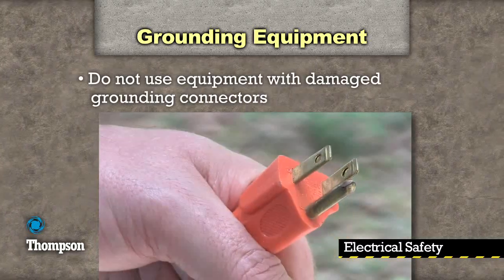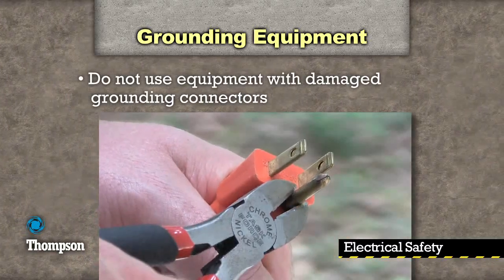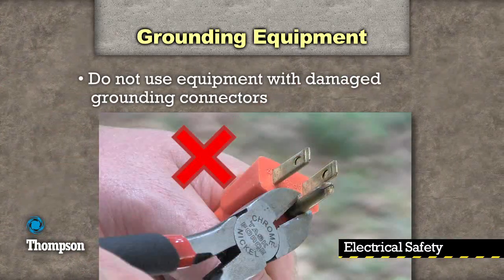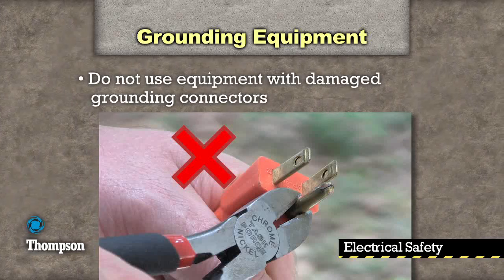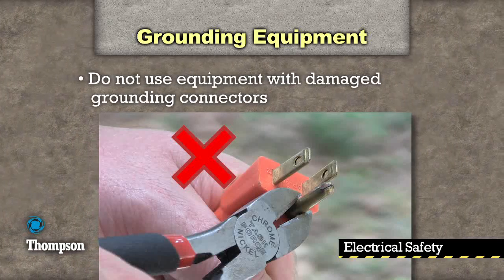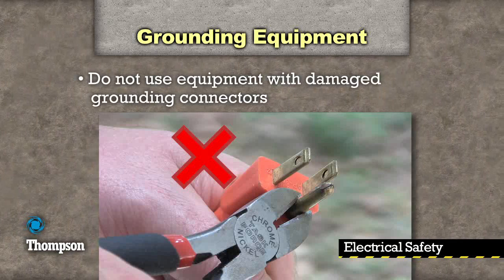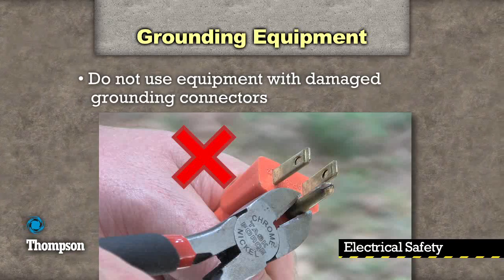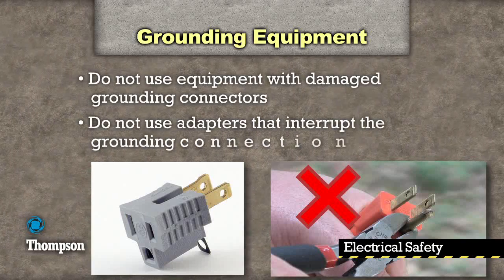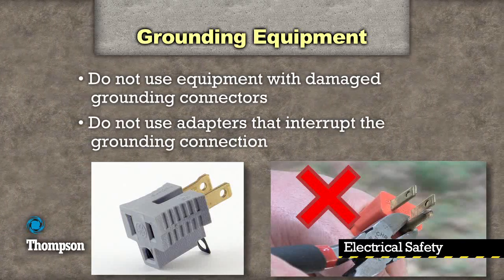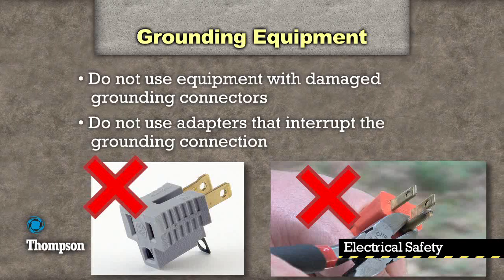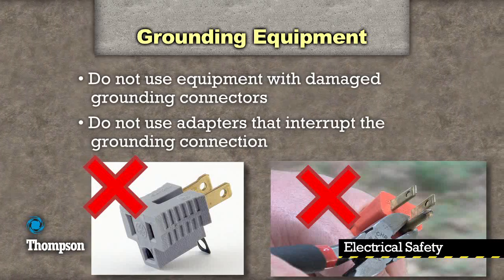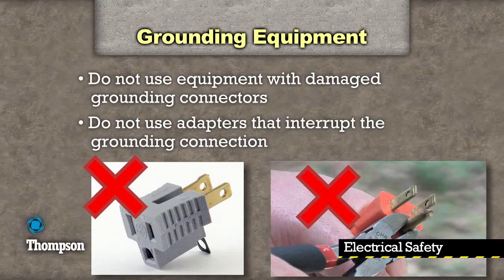Some people might alter a 3-prong plug by cutting off the grounding prong so that they can plug it into a 2-prong receptacle. This practice is not safe because they are bypassing an equipment safeguard and setting themselves up for an injury. Another mistake is using an adapter to convert a 3-prong system into a 2-prong system. Again, this interrupts the grounding connection. The adapters are not designed to send the current to ground if there is a problem.